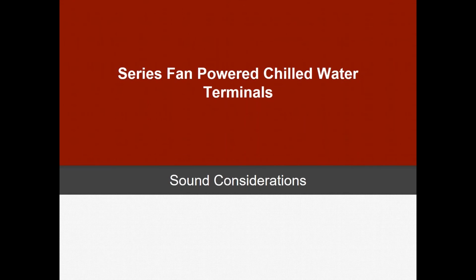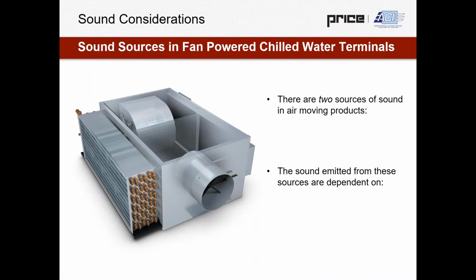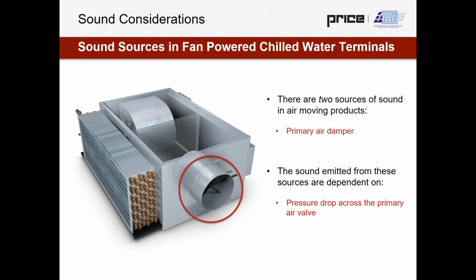Another major component of this equipment, which I think is maybe a little bit undervalued or overlooked, but Price takes very seriously, is sound. When we look at a fan-powered chilled water terminal, there are 2 sound sources. There's our primary air damper, and the sound emitted from that source fluctuates with the pressure drop across the primary air valve and also the volume of air across that air valve. And then there's the motor and blower assembly, and the sound emitted is dependent on where the fan is operating within the fan curve.